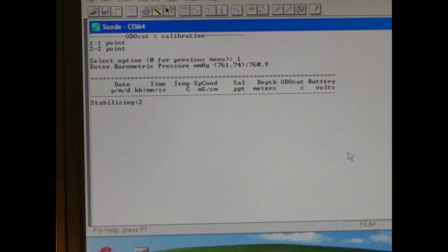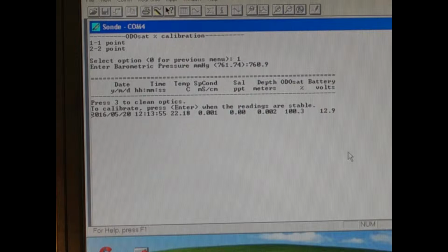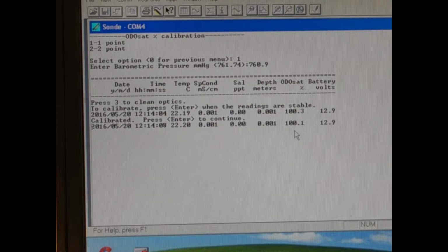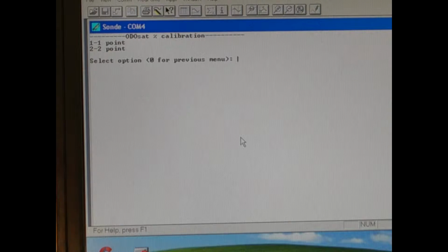So now it's going to give us an initial reading, which we'll write down on a calibration sheet. The initial reading is 100.3. And we push enter. And now it is calibrated to 100.1. The temperature, which we do have to write down, is 22.20. So now we have calibrated our DO sensor.